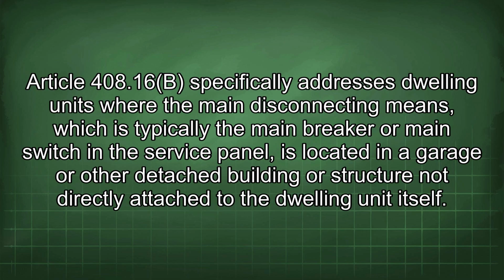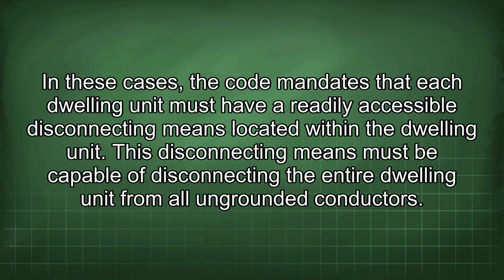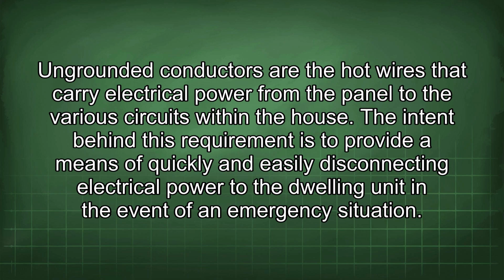Article 408.16b specifically addresses dwelling units where the main disconnecting means, which is typically the main breaker or main switch in the service panel, is located in a garage or other detached building or structure not directly attached to the dwelling unit itself. In these cases, the code mandates that each dwelling unit must have a readily accessible disconnecting means located within the dwelling unit. This disconnecting means must be capable of disconnecting the entire dwelling unit from all ungrounded conductors. Ungrounded conductors are the hot wires that carry electrical power from the panel to the various circuits within the house.